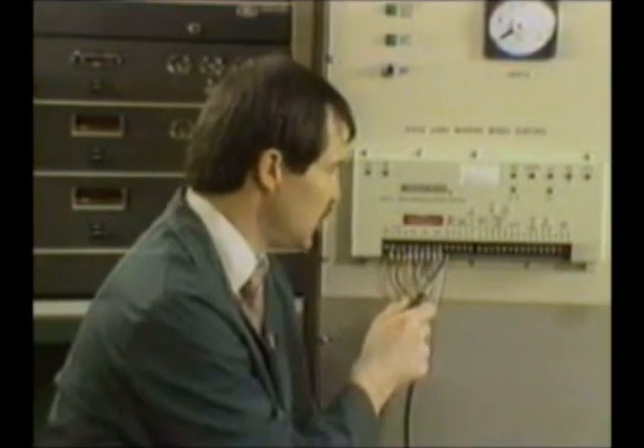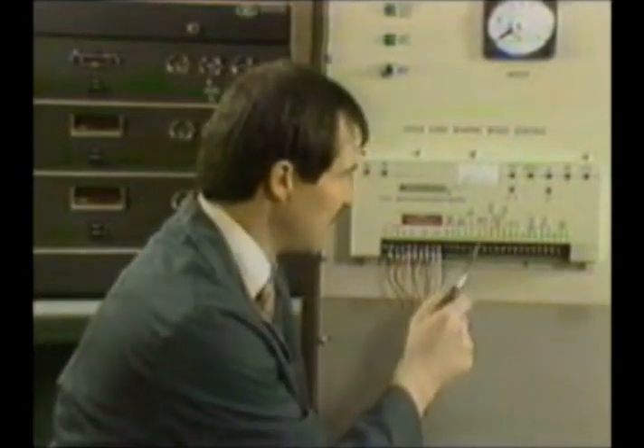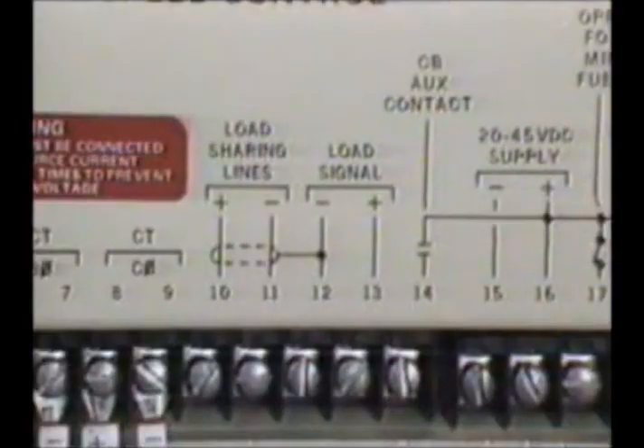And if you connect the shield to the 2301A control, at the other end of that cable, that shield should not be hooked to anything. The shield will be terminated here at our control. And we point out very clearly on here where we use those shields. Terminals 12 and 13 are also your load gain signal. This is where you set up so at maximum capability, you set up your load gain so that each unit will load share proportionally.